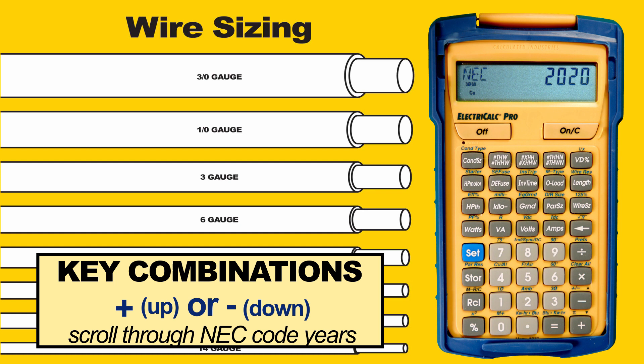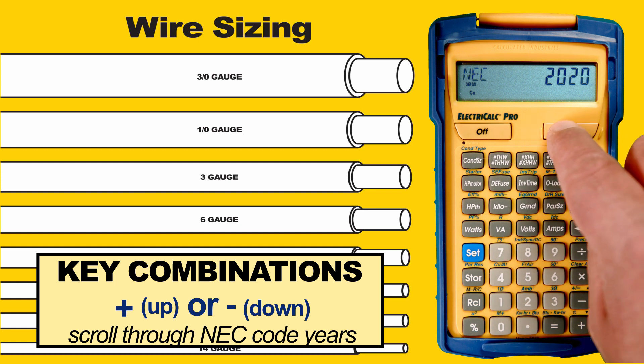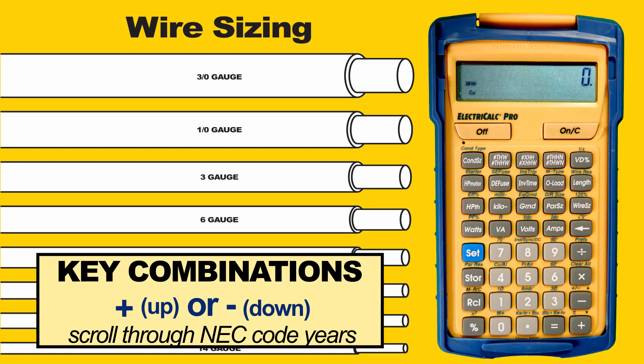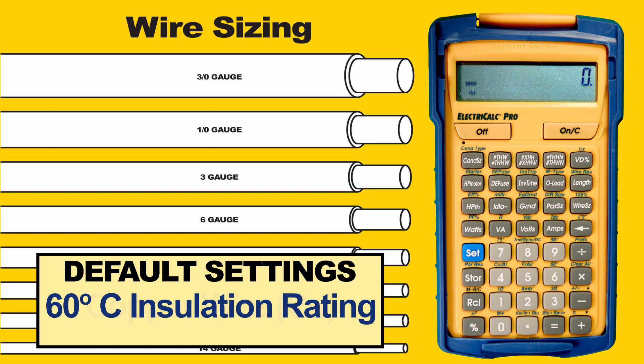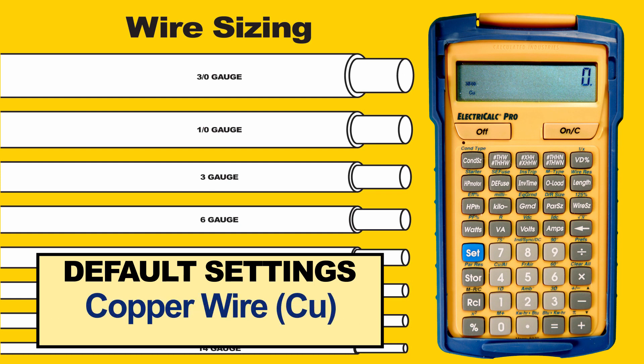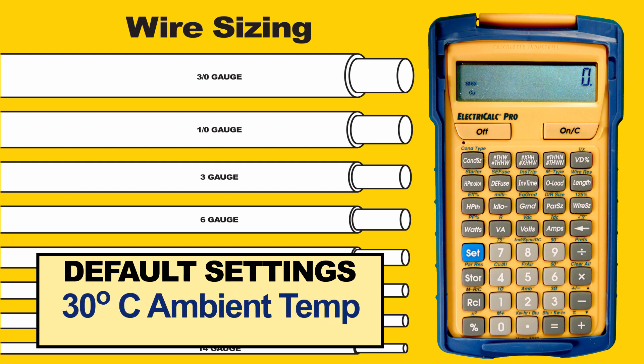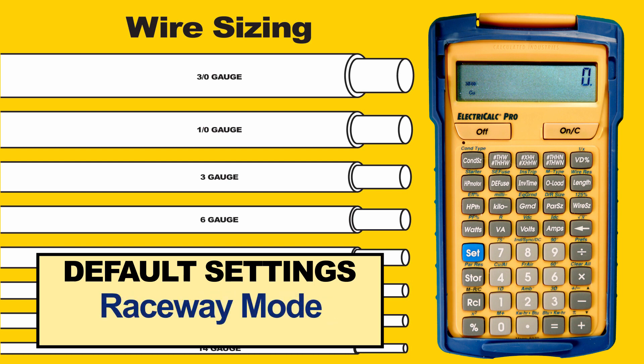We'll press the On/C button to clear the screen, but all the settings will remain in place. On the left side of the display we can also see some additional default settings, which are always displayed here. Three-phase is the default, as is a 60°C insulation rating and copper wiring. Other defaults not indicated on the screen are ambient temperature at 30°C and raceway mode as opposed to free air mode, so we will be working off of Table 310-16.